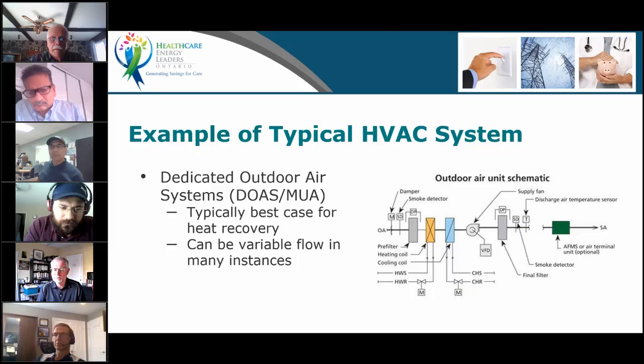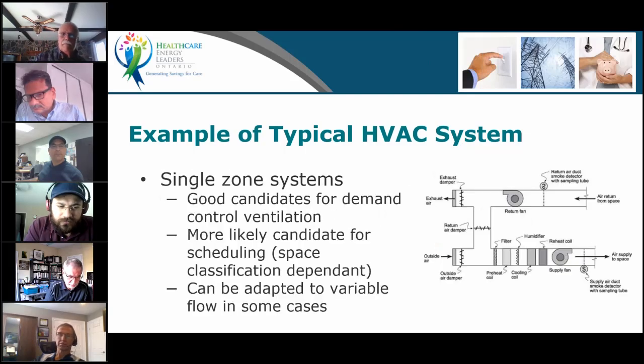When you have a system like that, if you have a heat recovery chiller, you can cool your exhaust with your return chilled water line and capture that heat in your chilled water, which will then dump it to your condenser that can then be used to heat the building. So you do indirect heat recovery. Makeup air units can be good for that, or any exhaust that you have can be good for that.